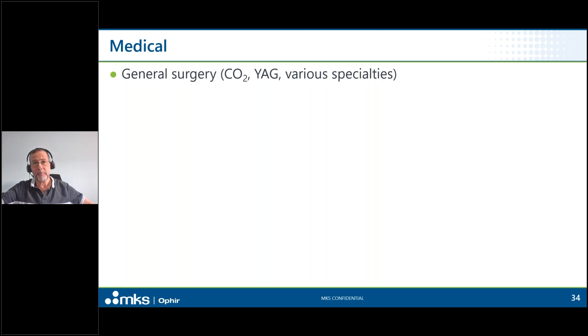When we think of laser-based medical applications, probably the first ones that come to mind involve surgery, CO2, YAG, some specialty type of lasers. CO2 is still the laser of choice in applications where the target tissue is very close to important non-target tissue, including many laparoscopic procedures like gynecology. CO2 long wavelength, like 10.6 micrometers plus minus, has a very shallow absorption depth, meaning it's very readily absorbed by water, and our tissues are to a very large extent made of water. So that makes it easy to be highly specific and to minimize thermal risk to nearby tissues that I don't want to heat up, burn, cut, weld.